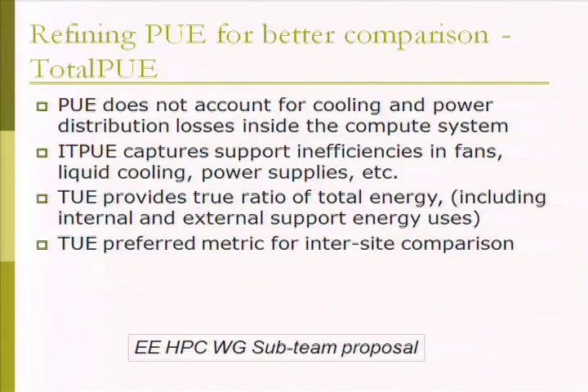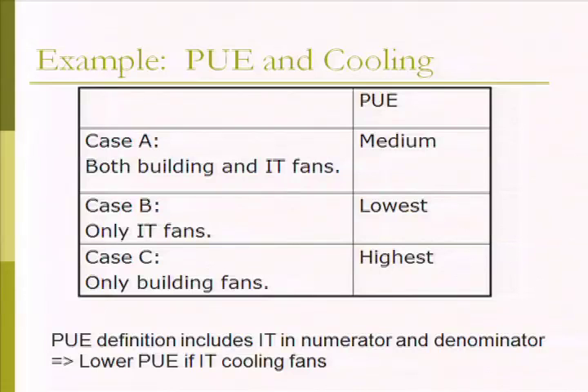So just to give an example: because IT is in the numerator and the denominator, if you only have IT fans, your PUE will be lowest. If you only have building fans, your PUE will be highest, which is bad. High PUE is bad. A medium case is where you have both building and IT fans.